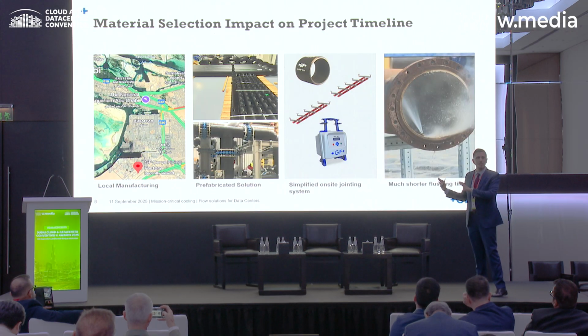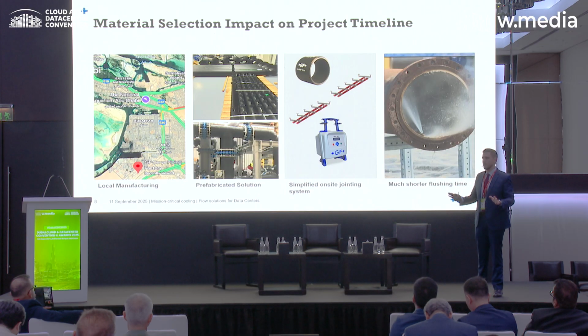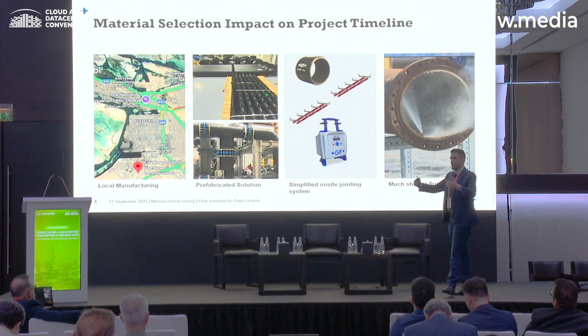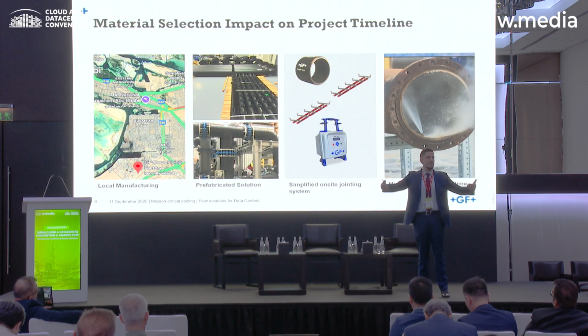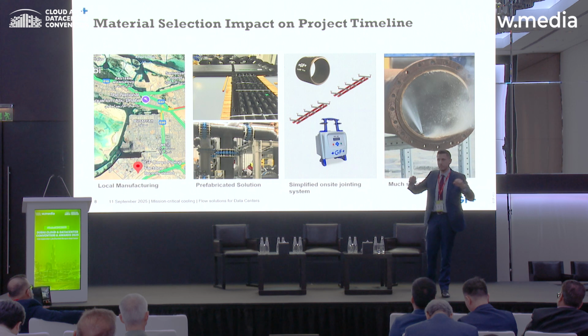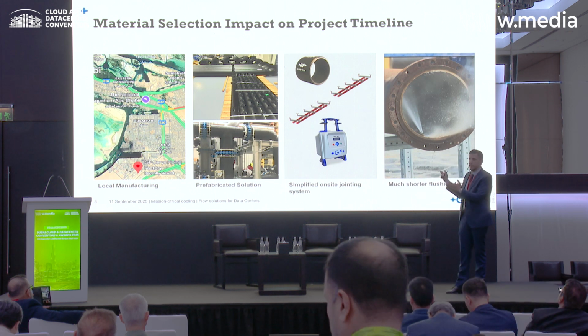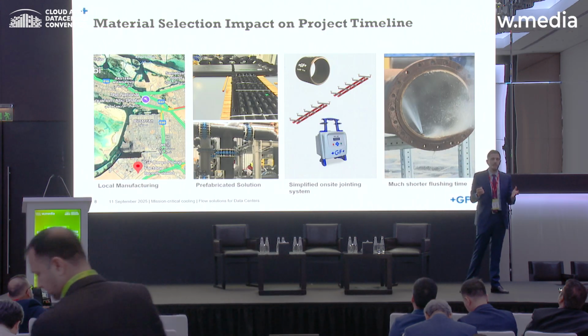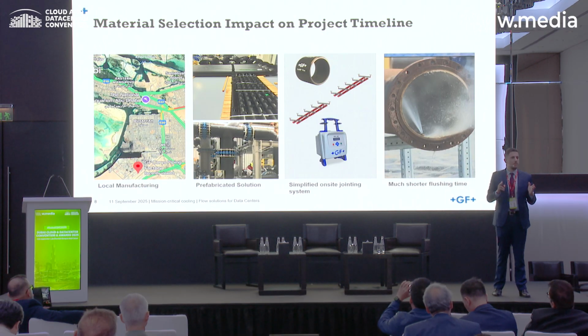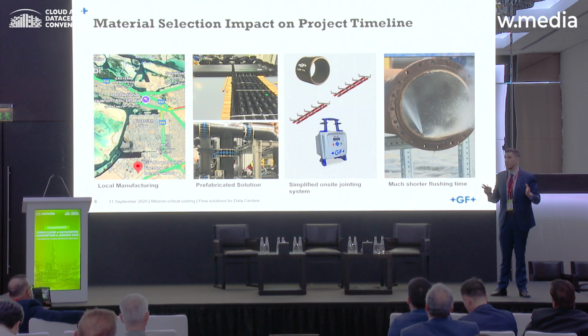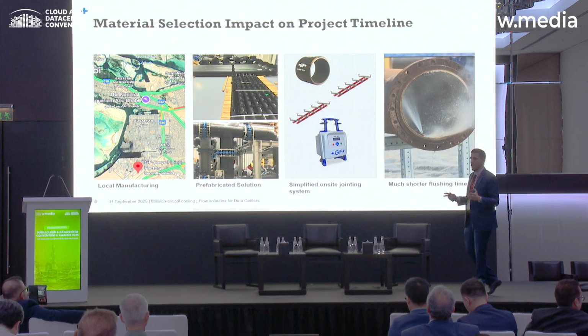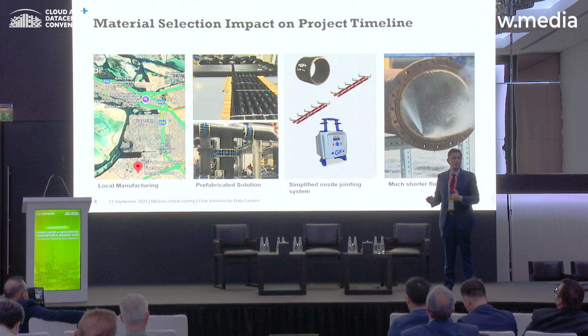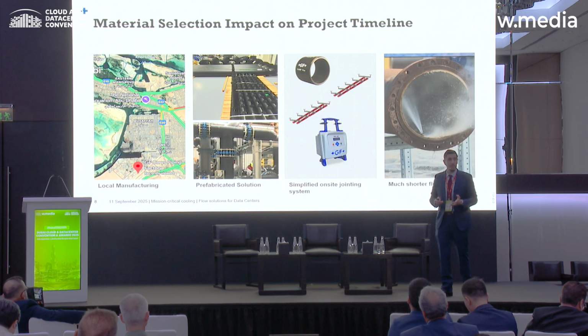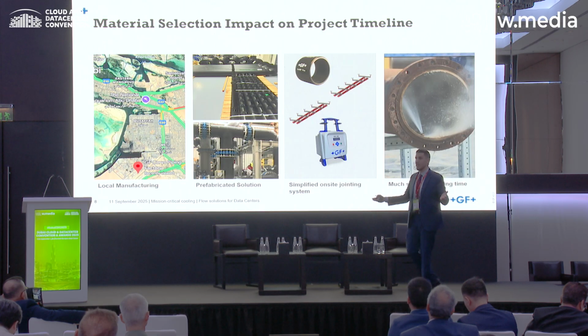When it comes to flushing, this is a different subject. At the time, I have two systems ready to be commissioned from a jointing and installation point of view—one in HDPE, one in carbon steel. I need to do the flushing protocol. In HDPE, it's a one-week requirement for static flushing with simply water, no matter how big the network is. With carbon steel, we're talking about a strict protocol involving static and dynamic flushing with water and chemicals, which can stretch to weeks and months.